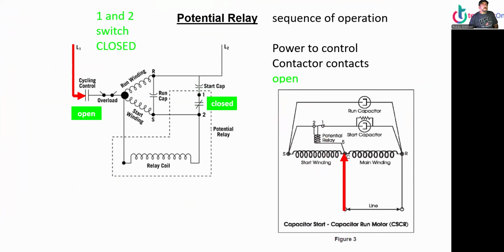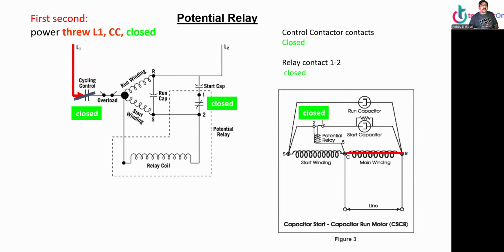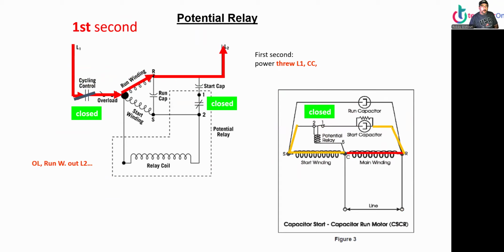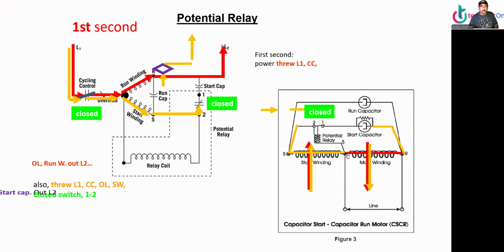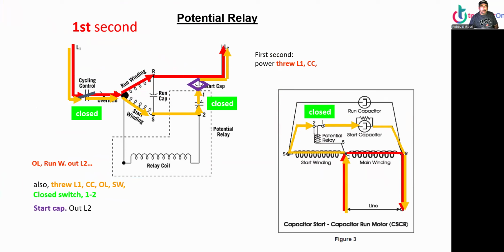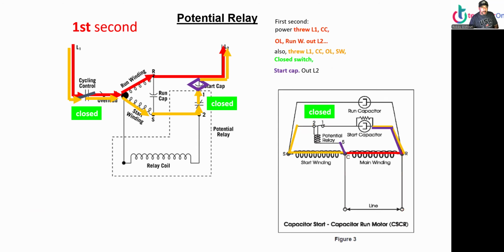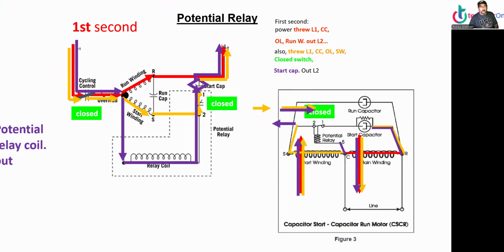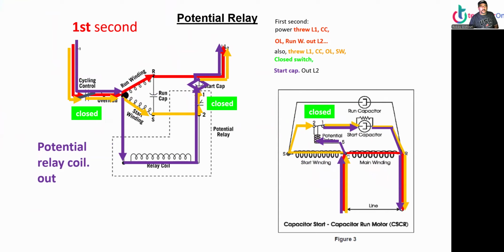All righty, so sequence of operation: 1 and 2 is a switch. Power comes in, but now control is open. The switch is always closed between 1 and 2. It starts closed. Power goes in now, the contactor is closed. First it goes to the run windings. Then, all of this is in the first second, power also goes to the start winding and to the normally closed switch and out to the start capacitor and out L2. And in the first second, power also goes into the relay coil and out. That's what's happening in the first second.